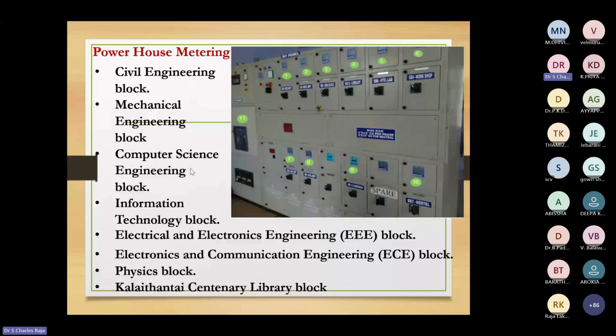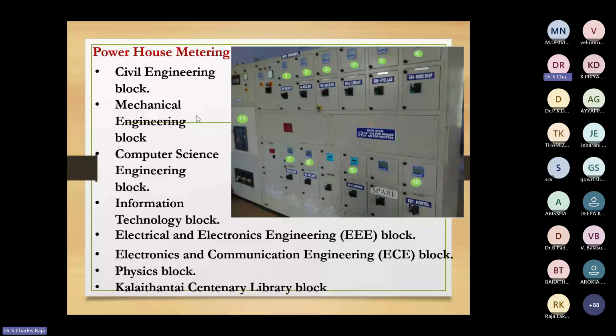These are the blocks we have in our college. In every block there is one feeder from the powerhouse metering, and in each feeder we fixed one smart meter. Each smart meter measures all the data, starting from voltage to power factor, and some low accuracy power quality based parameters can be measured using these smart meters.